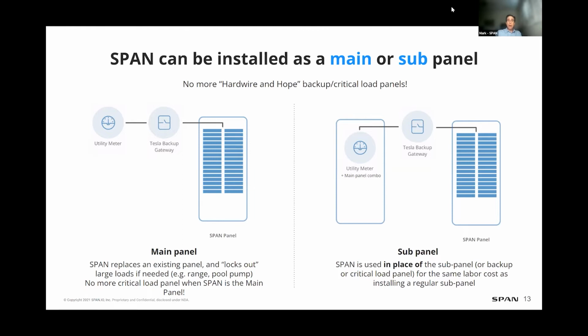On the other possibilities, if you have a meter combo panel, you can often use SPAN as the sub panel, and you can replace or move the circuits from that main combo panel. If you're upgrading, you can treat the utility combo panel as the meter main entrance. This shows you some configurations and battery backup.